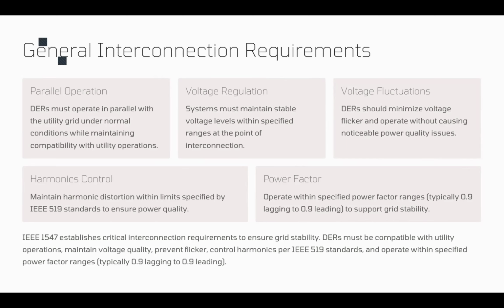We have a voltage fluctuation aspect, where the DER basically has to minimize voltage flicker and operate without causing power quality issues. Another aspect was harmonic control. We said that they have to maintain their harmonic distortion within the limits, and we said those limits are specified in IEEE 519. We also mentioned another requirement, which is power factor. Okay, so they have to operate within a specified range for power factor. We said it's typically 0.9. It could be lagging or leading, doesn't matter, but it should not go lower than 0.9.